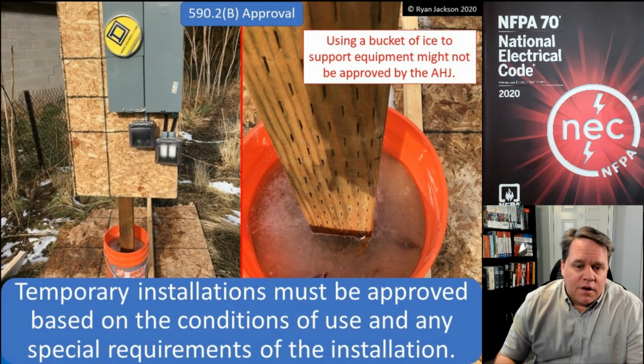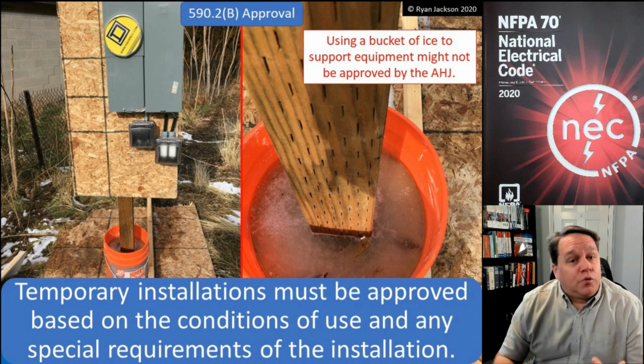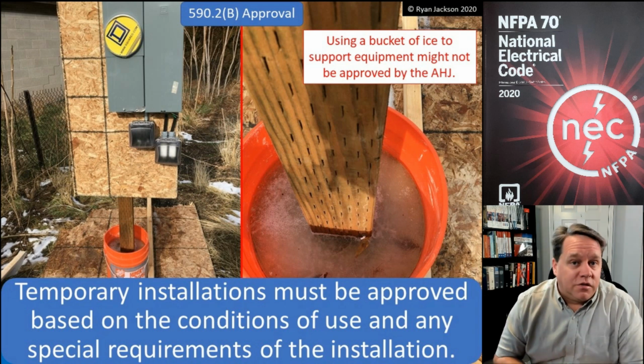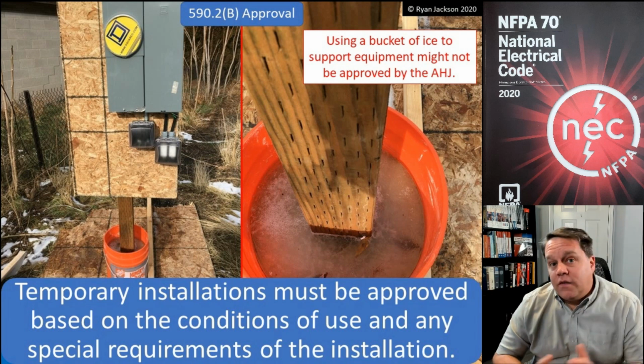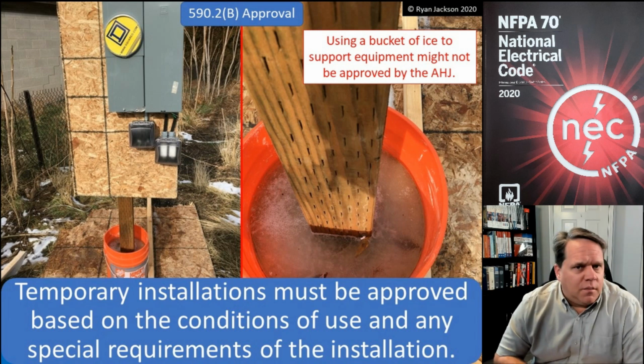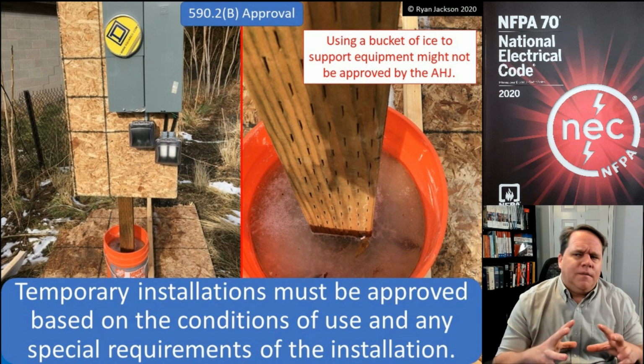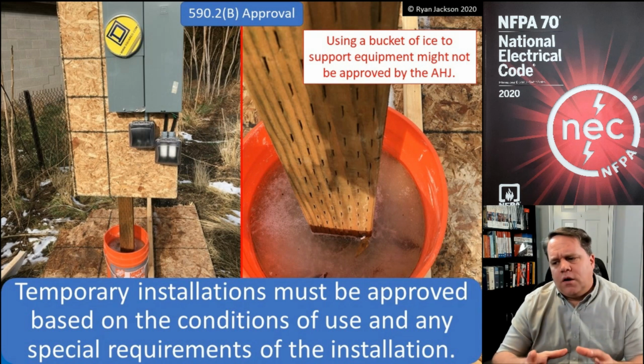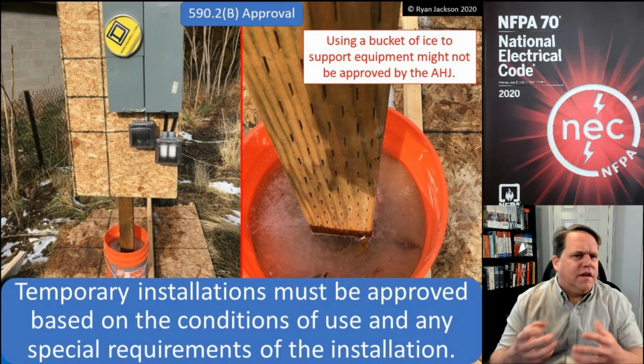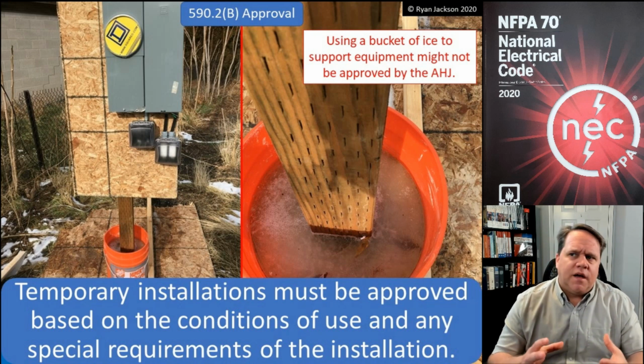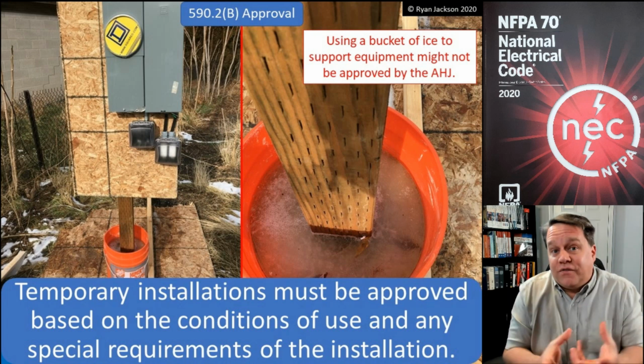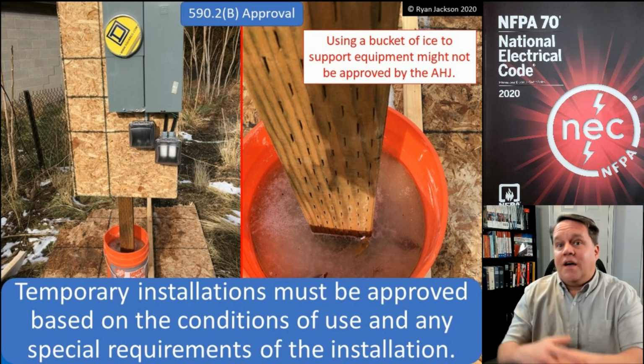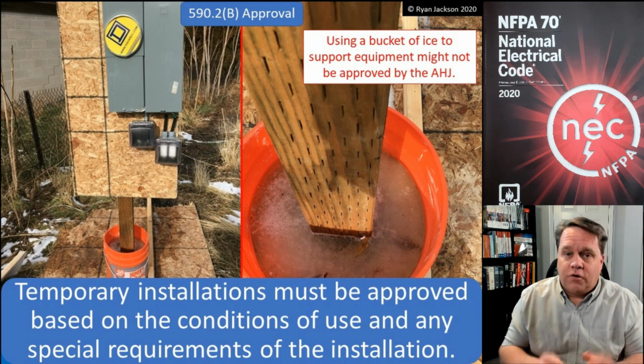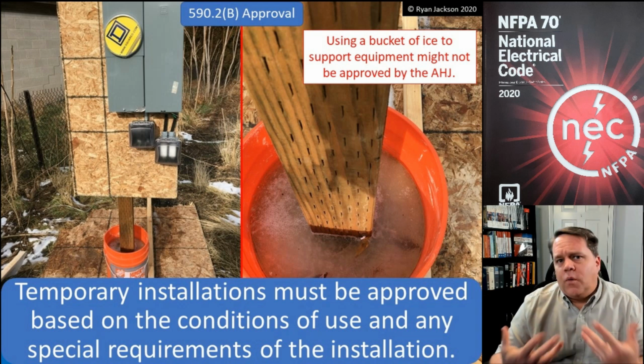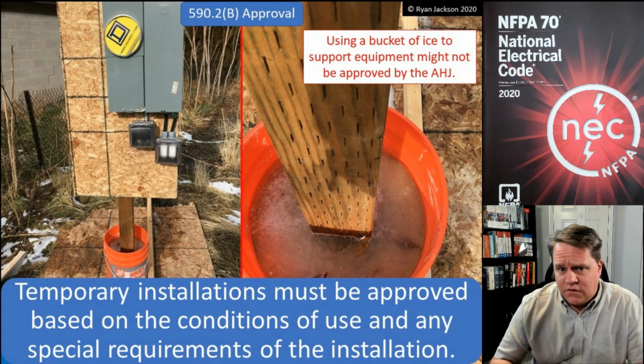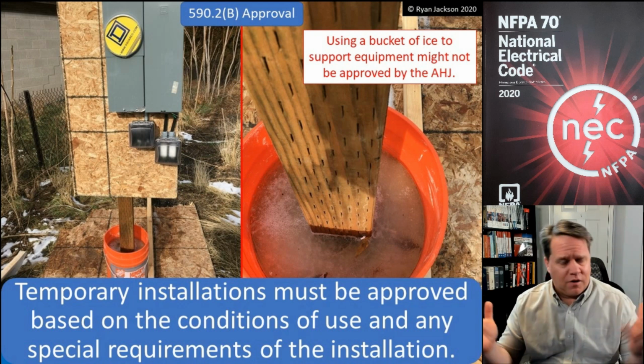590.2(B) approval. Temporary installations must be approved, which is acceptable to the authority having jurisdiction, based on the conditions of use and any special requirements of the installation. It's hard enough to write code that covers every conceivable condition. We have to have a one-size-fits-all code book that applies to everything, and that's pretty difficult, especially when you throw in things like temporary conditions, rain and snow and everything else.